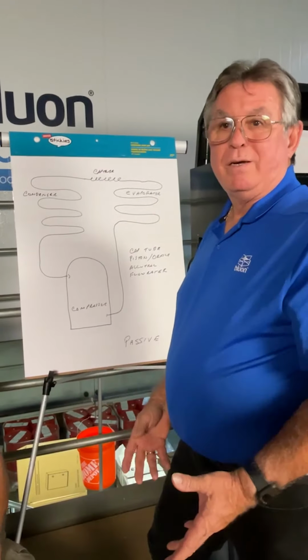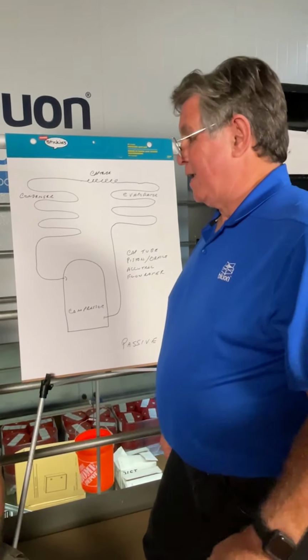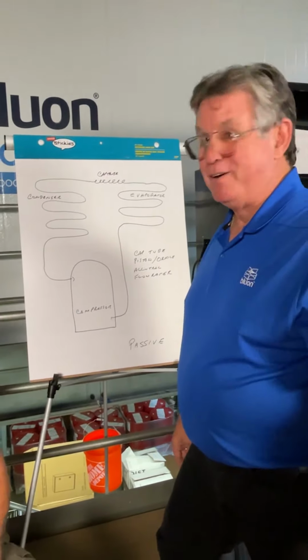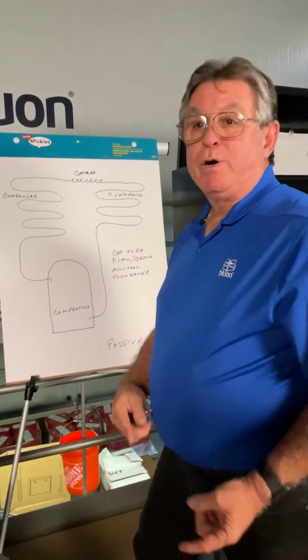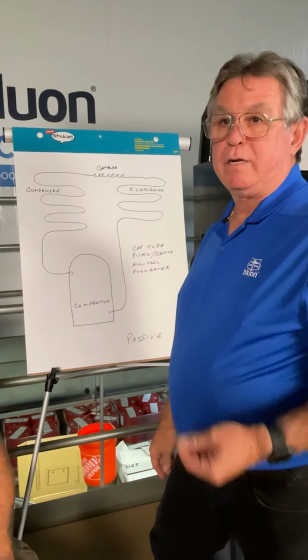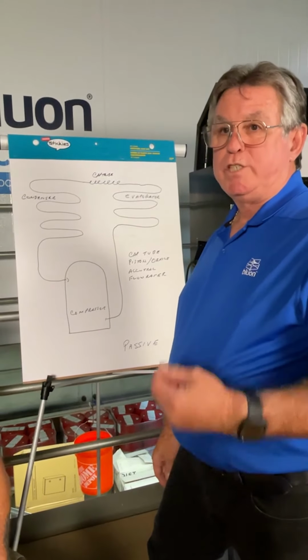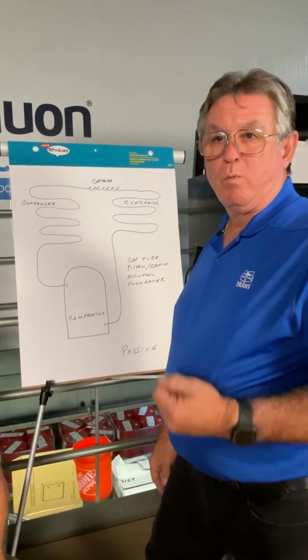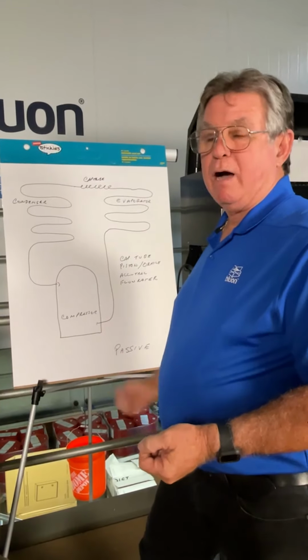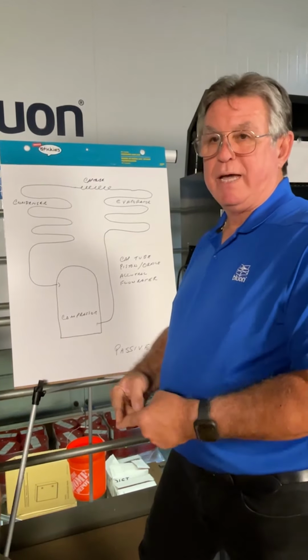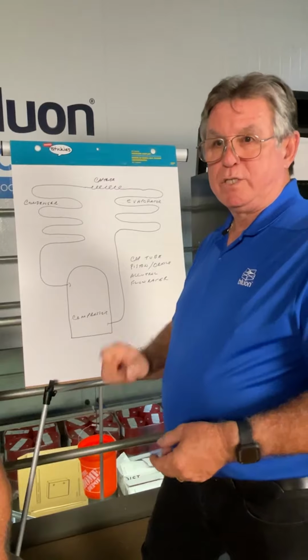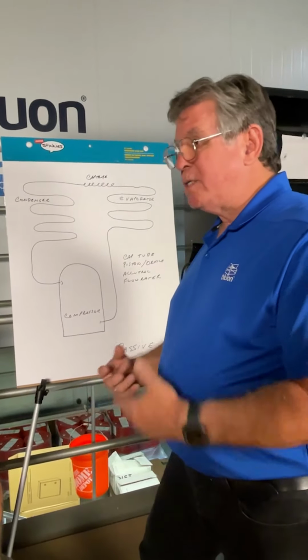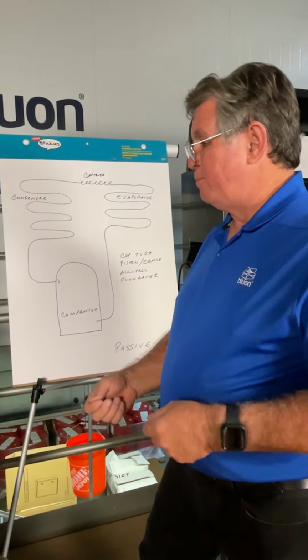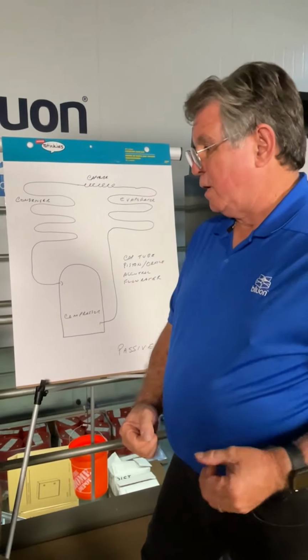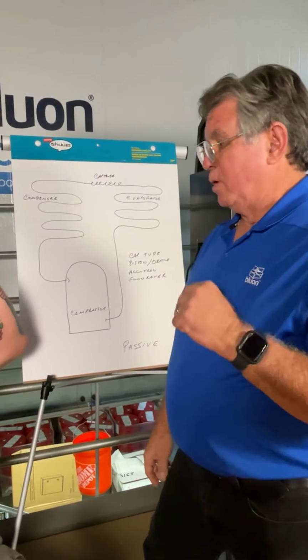So Bluon, gotta love those guys, gotta love those engineers and the people that do the app and everything else. Gotta love tech support. They turn around and they created a target superheat. And so what you do is you take the return air wet bulb and the outdoor air dry bulb, and you plug that in, and it'll give you a target superheat. Now, we've run into some people that don't have ways of measuring return air wet bulb. And there's one, go ahead.